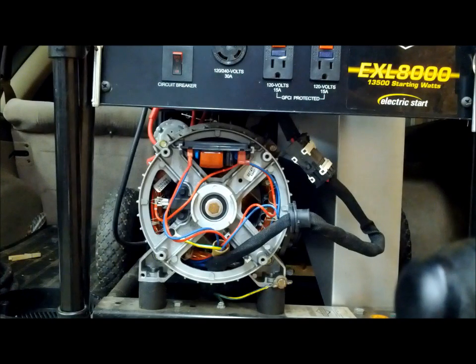Before reinstalling that cover, I suggest pushing it outside, starting it up, let it stabilize at its running speed, grab something small and let's load test it, make sure it's generating electricity. If it is, you can go ahead and reinstall that cover. If it isn't, you lost the residual magnetism.